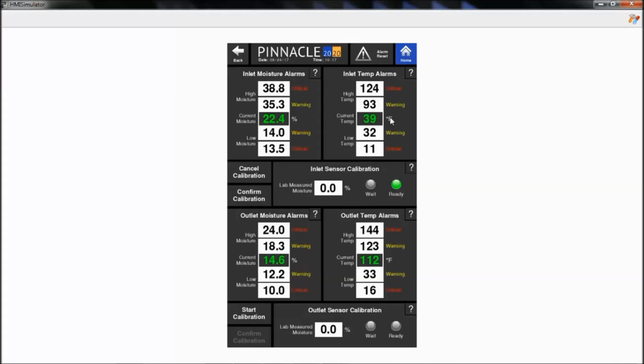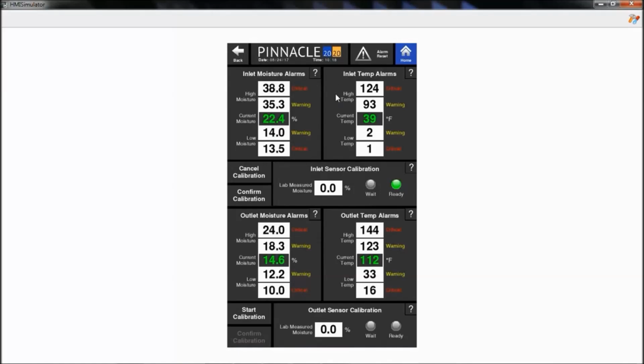For instance, your setup may not be concerned with inlet temperature. Most setups aren't. So you have no reason to set these alarm limits too close together, or you'll end up having nuisance alarms. We've put all of these alarms in here so that anybody who wants to use them can. If you're not interested in monitoring a certain value, you can change your numbers down to very low numbers that you won't expect to see, and you shouldn't experience that alarm. So one of the important things to do prior to starting up is to identify which alarms are important to you and the site you're working on, and set them accordingly.